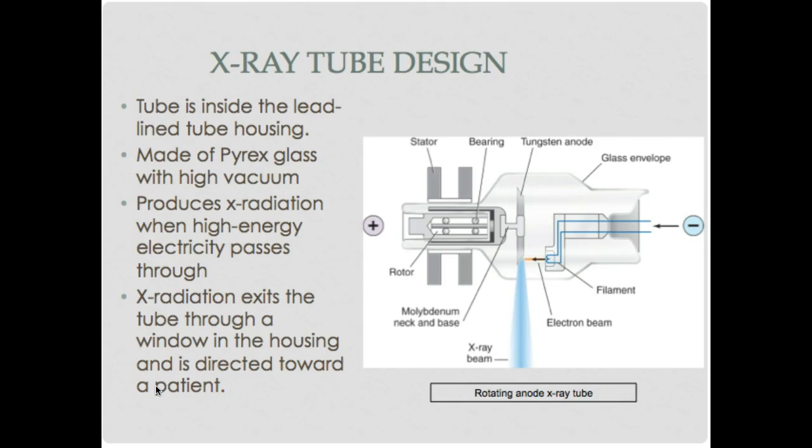The anode is a tungsten-rhenium track. Tungsten handles the high heat, and rhenium handles expansion and contraction due to that heat. There's a molybdenum base with bearings and a stator, and we use magnetic induction to spin the anode. Outside the x-ray tube there is a lead-lined tube housing to absorb and scatter radiation. X-ray radiation exits the tube through a window in the tube, and there is also a window in the housing directed toward the patient.